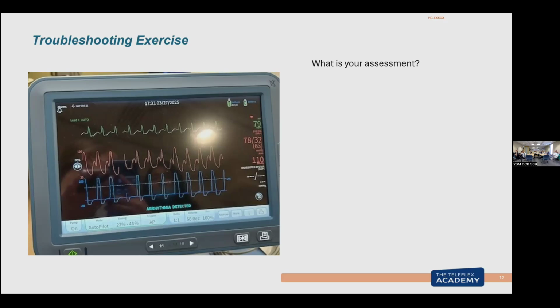On this one, a couple of things you can see. Yeah. Sorry. Is there any automation to the machine augmenting the volume that it's filling the balloon, or is that only manual and something that I can't increase? Because what you're used to on the other pump, that's a pressure pump. And so the augmentation that you're adjusting is not volume, that is pressure on that. That pump will deliver 60 to 70 cc's every time the balloon goes to inflate, regardless of the size balloon you put in.